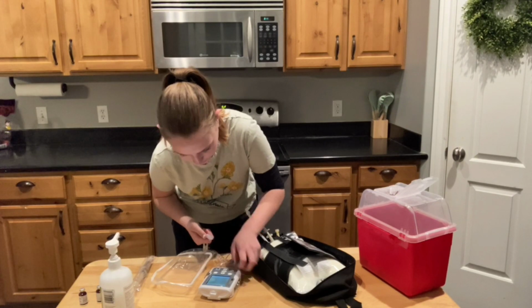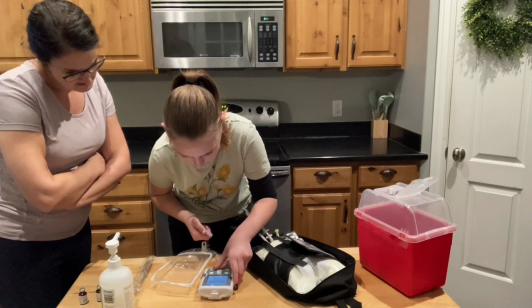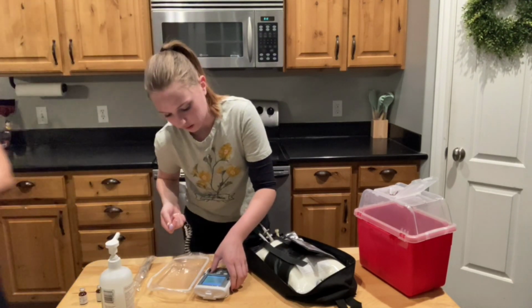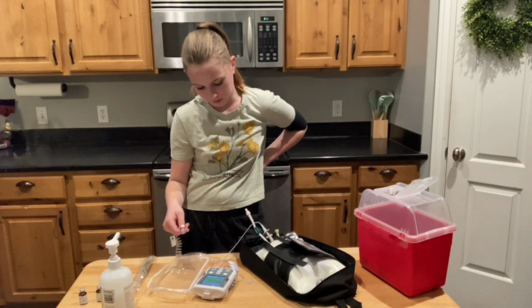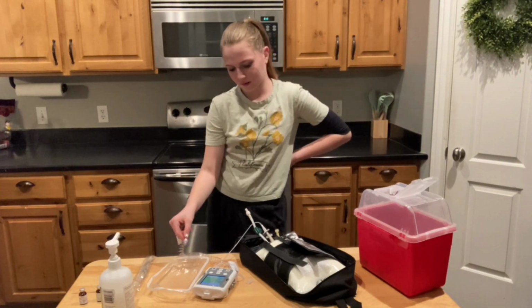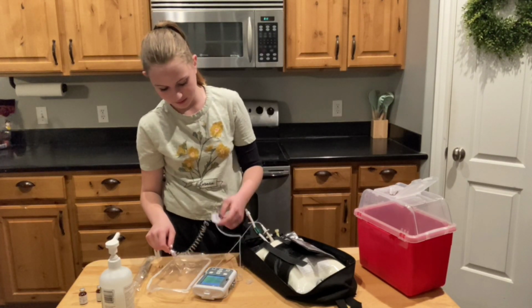No, I'd like to prime you. How do I prime you? I forget. Ah, now I remember. Go down to prime tubing. Select. Uncap. Prime. That's not the right button. Prime. I'm assuming this is going to take a little bit faster considering it's the same length of tubing it's got to get through.